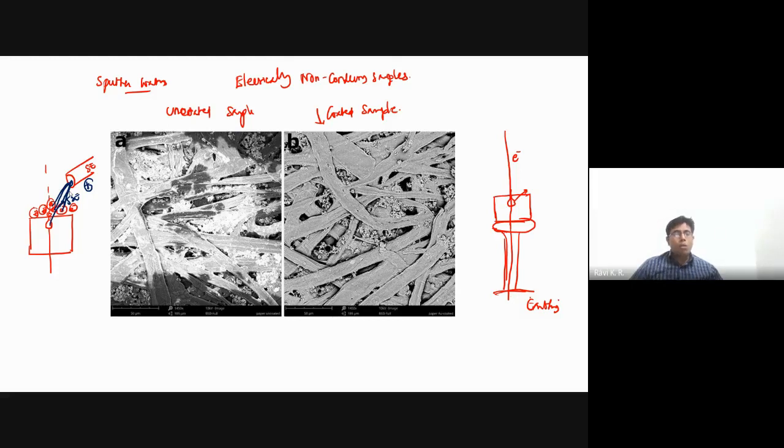So now you start seeing the image brighter. Bright means the number of electrons coming out is larger and larger. Now it is not only the secondary electrons coming out from the sample that go to the detector. There are other electrons which are accumulated on the sample surface. That is also influencing your image. That is the reason you don't see the contrast. See, this is a coated one. This is an uncoated one.